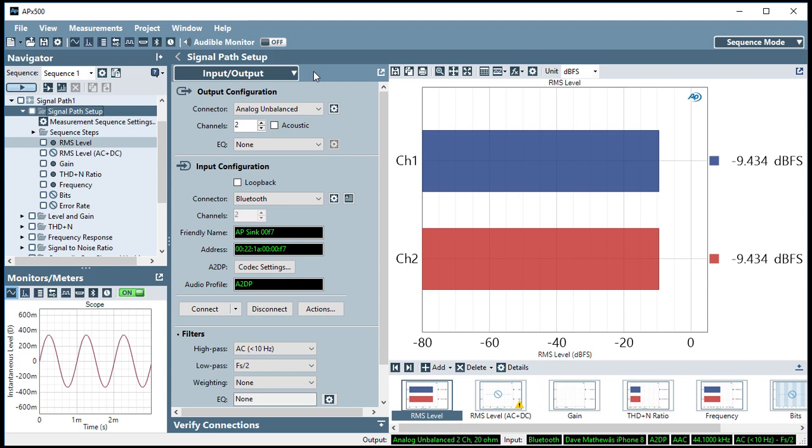and then play a test signal from a file I previously loaded on my smartphone. You can see the status monitor shows that it's streaming, and you can see the waveform in the scope monitor. Now I'm ready to make open-loop measurements on the streaming Bluetooth audio data presented to the APX Bluetooth input.